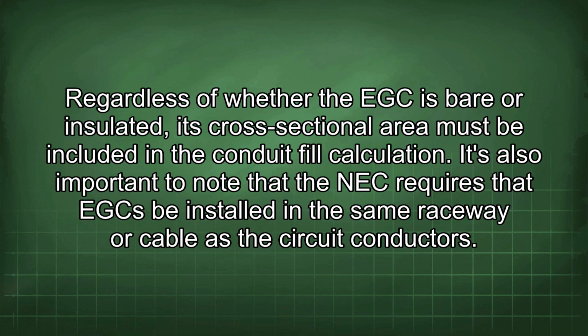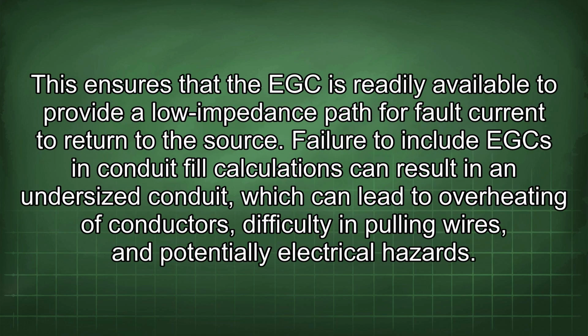It's also important to note that the NEC requires that EGCs be installed in the same raceway or cable as the circuit conductors. This ensures that the EGC is readily available to provide a low impedance path for fault current to return to the source.